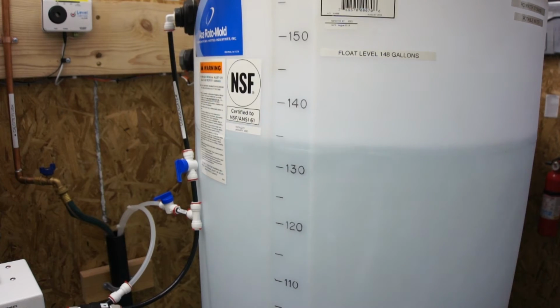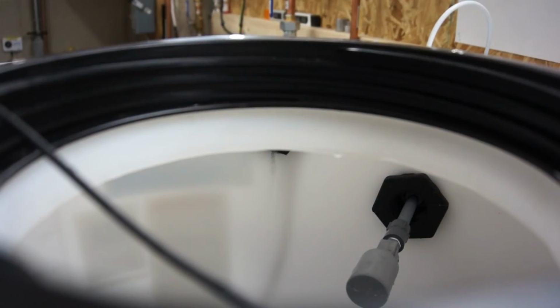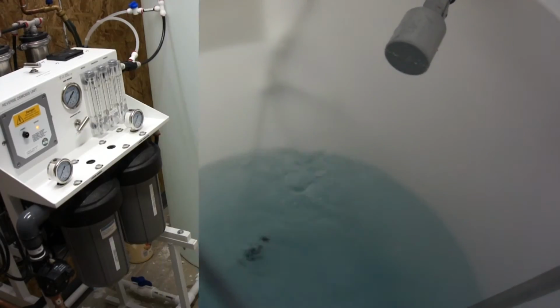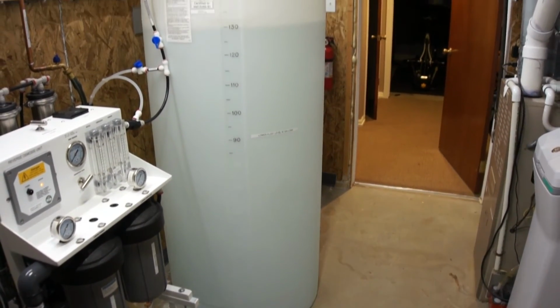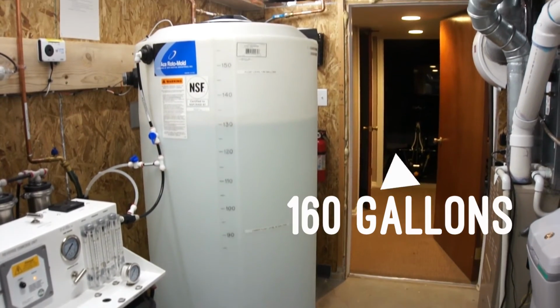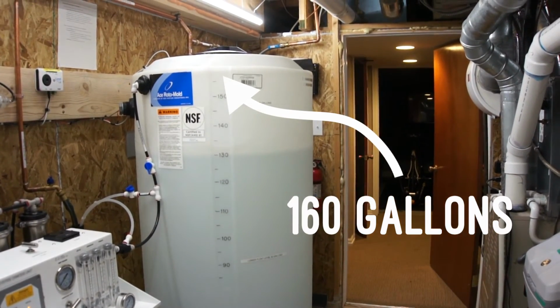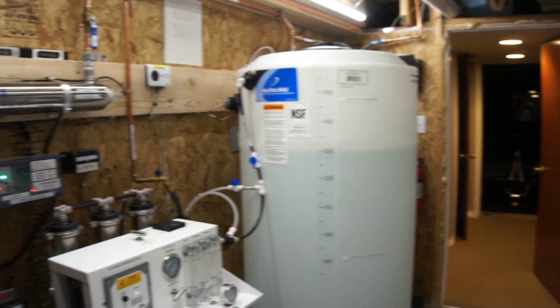The RO system, though, is quite effective. It reduces the TDS from 1900 to around 18. I'm using a 160 gallon tank to store the fresh water. Our house uses about 500 gallons per day, and this tank is about the right size.